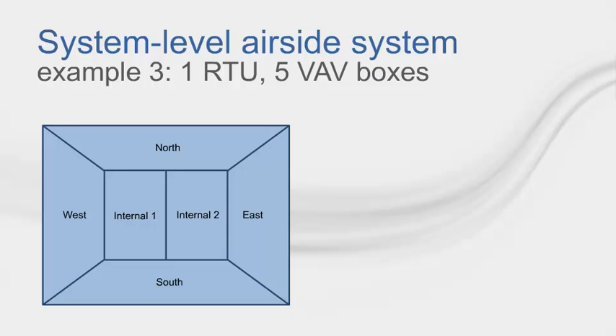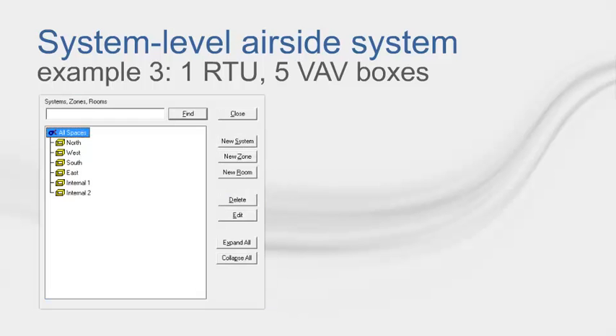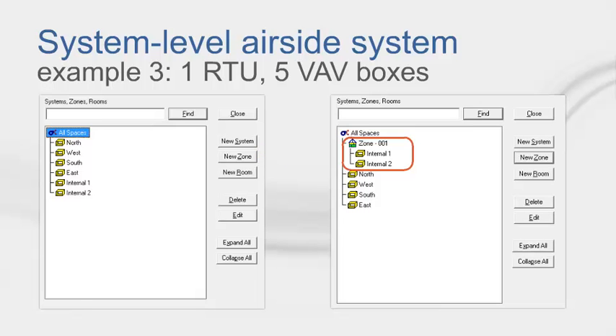For our last system-level airside system example, let's imagine having one VAV box serving more than one space. Both internal spaces will be tempered by the same VAV box. To have two or more rooms covered by one VAV box, the creation of a zone is required. Simply create the zone by hitting the New Zone button and placing the two rooms underneath it. Note the system that is selected is the system that will receive the new zone. To model this example for energy analysis, you will also have to specify a thermostat location of zone for all the rooms served by the same terminal device.